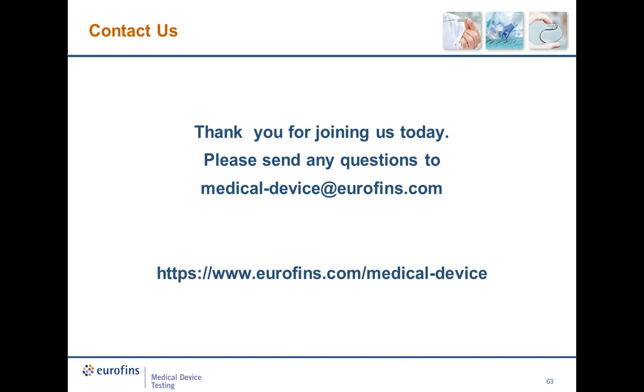You mentioned gas pathway device. How should we approach the biocompatibility of this kind of device? Okay, let me start. So the ISO 10993 series, as you know, is intended to cover the biological evaluation of medical device. However, gas pathway device pose peculiar risk, and the ISO 10993 series does not address the biological evaluation of those devices in a specific way. So as mentioned by Matthew, we should refer to the ISO 18562 series to evaluate the biocompatibility of gas pathway device. ISO 18562-1 covers the general principle regarding biocompatibility tests. Then we have three other parts, part two, part three, and part four, that cover specific tests, and I think that Matthew could add something on that.